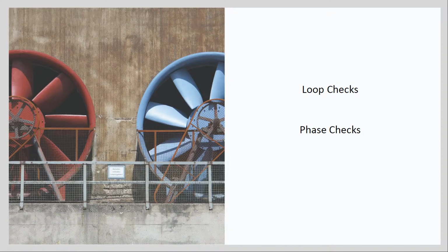So moving on to protection relay testing. Protection relays are used within electrical systems to monitor voltage and current and provide rapid response to safe the system should there be any fault detected. So what the relays do is they monitor the electrical properties of the systems, primarily through PTs or CTs, to measure voltage and current of the system, and they sense any disturbances that are in the system and react accordingly according to the settings that are applied to the relay.